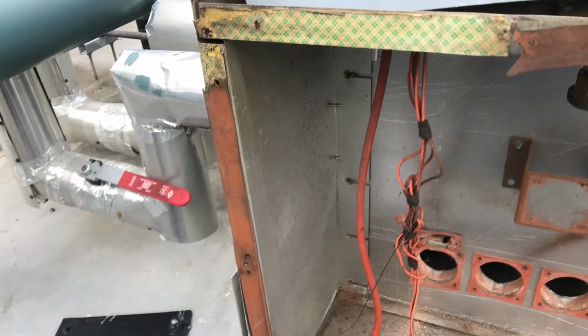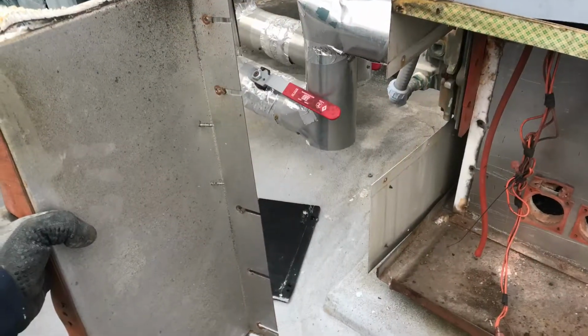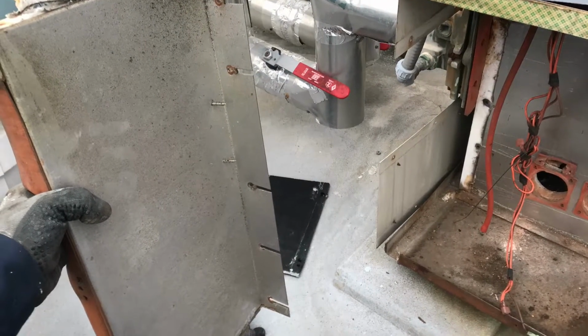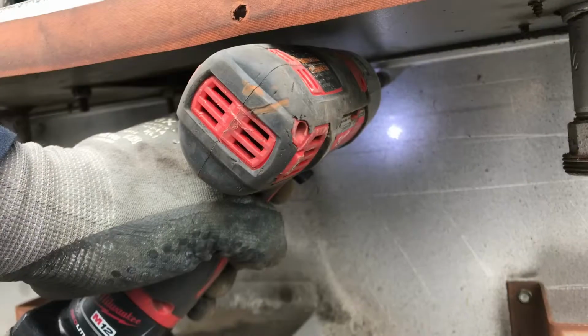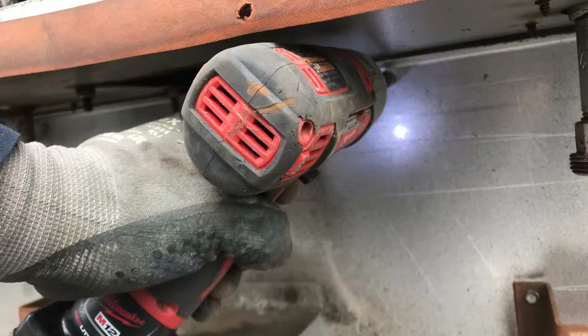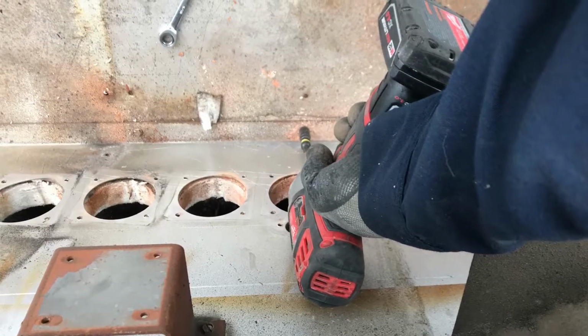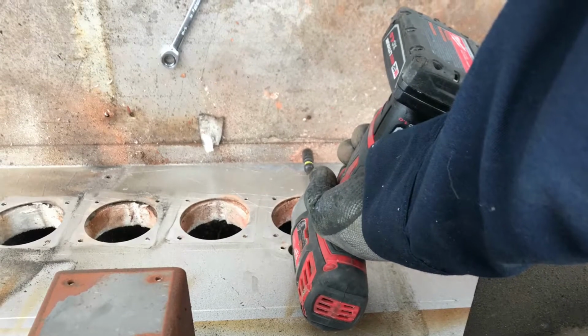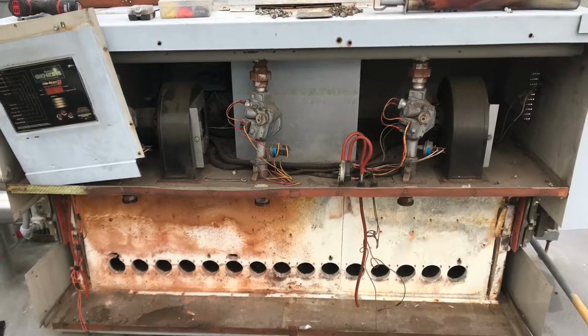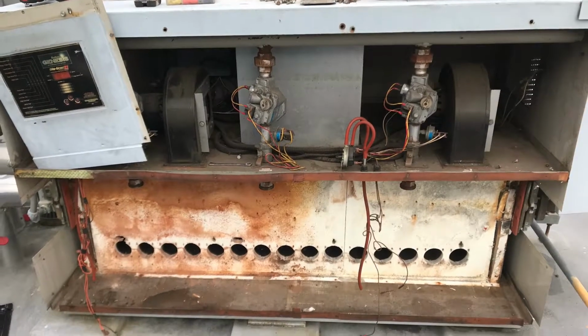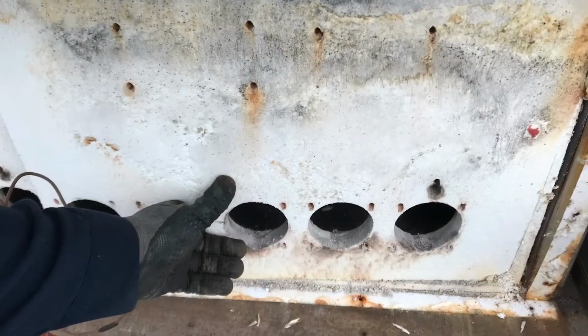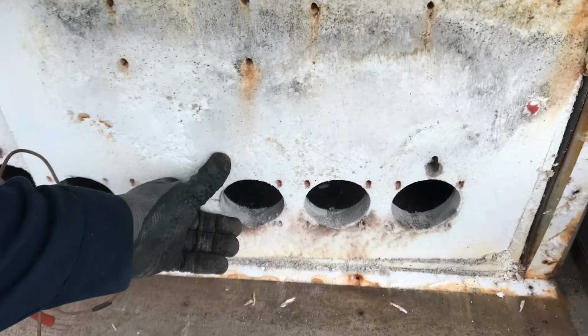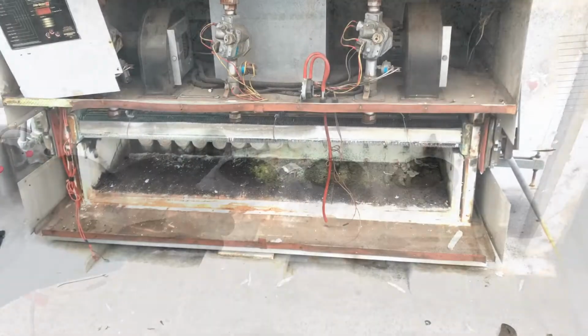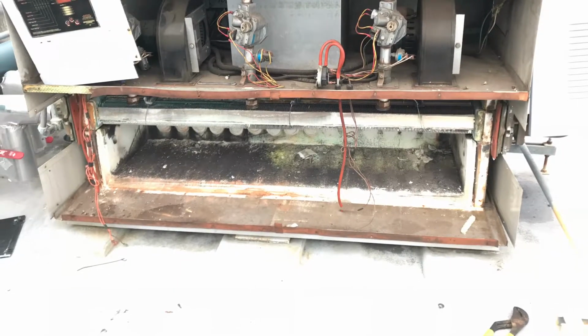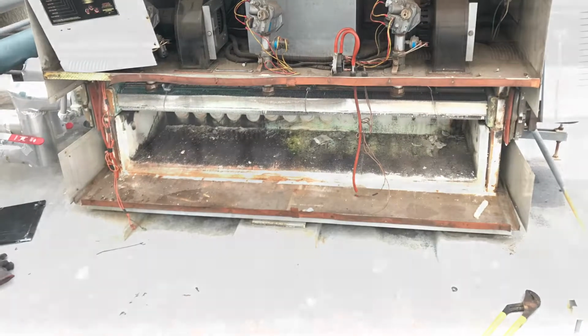So move the wires out of the way as needed, and you're going to remove the 2 side plates on this unit, which will completely expose the cover that's covering the heat exchanger. So you will remove that cover, and what you're left with is the refractory. You carefully pull the refractory off, and this exposes the burner cabinet and above the heat exchanger.